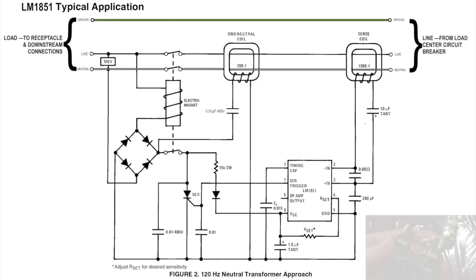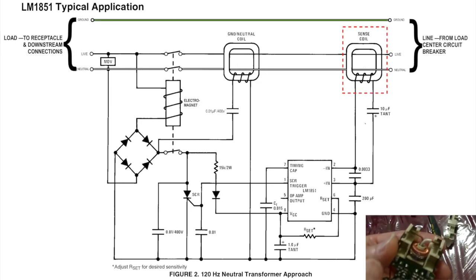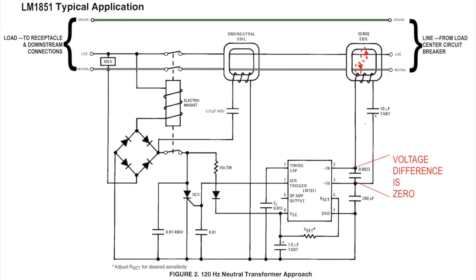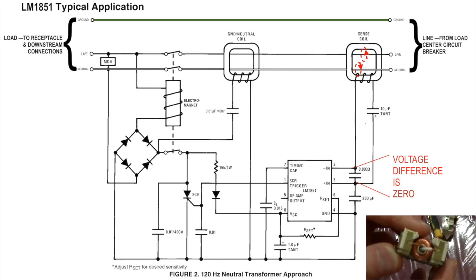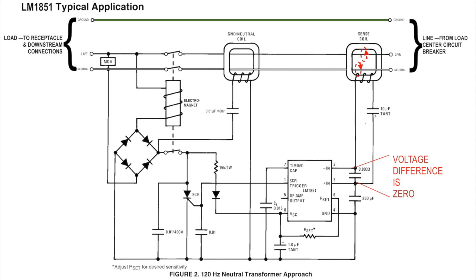Inside the GFCI, there is a differential transformer labeled sense coil. Under normal conditions, when there is something plugged in and operating, there's a current flowing on the live conductor and the neutral conductor. The currents are equal, but in opposite directions. Live and neutral pass through the differential transformer, but the magnetic fields created by live and neutral cancel each other out because they're equal and in opposite directions. Suppose, however, your grounded hairdryer drops into the sink, and current flowing into the hairdryer on the live conductor is now flowing out, both on the neutral conductor and the ground conductor.